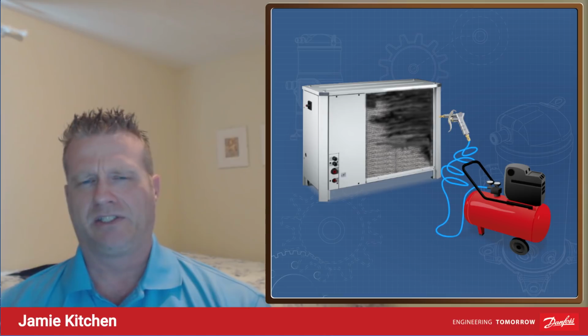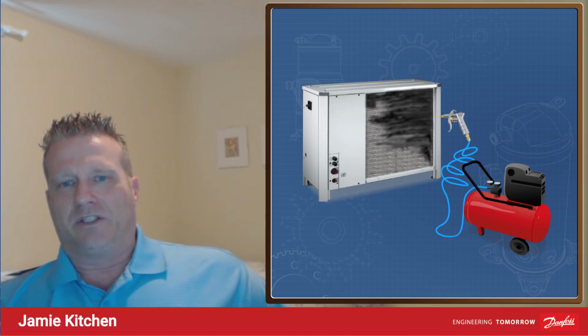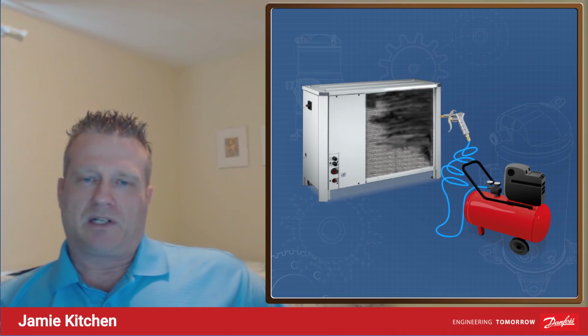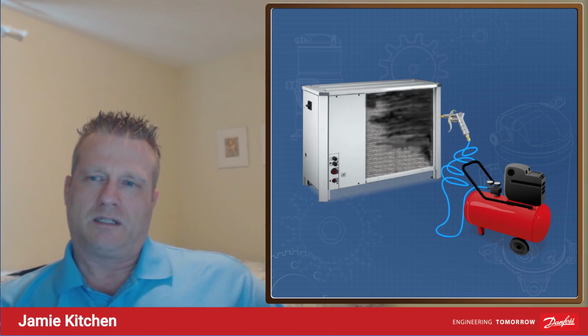Finding snakes and lizards and everything else living in these things, wrapped around the compressor relay. And the system is dirty. And when we clean all that stuff up and clean the condenser, we operate at about a 15 or 20 degree lower condensing temperature than we were before. So think about that, right?